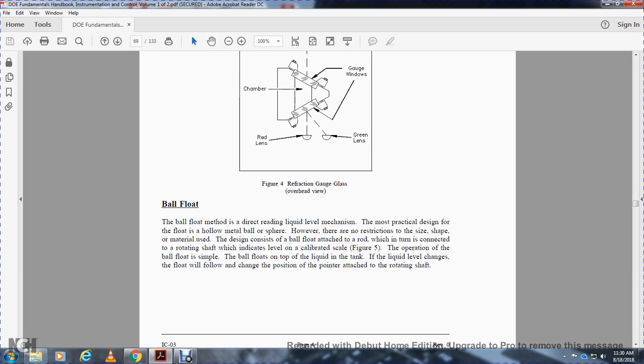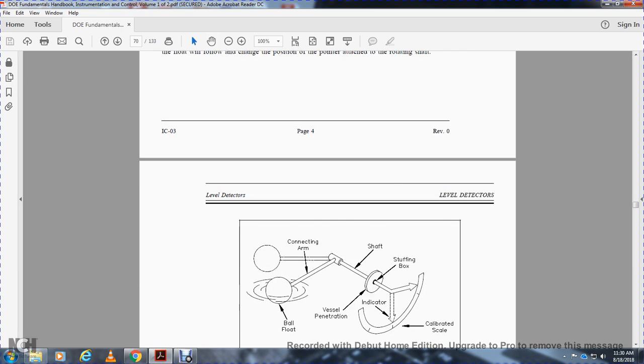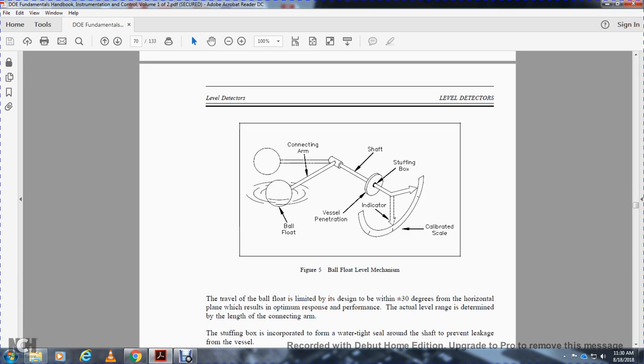The operation of the ball float is simple. The ball floats on top of the liquid in the tank. If the liquid level changes, the float will follow the level, and the position of the pointer attached to the rotating shaft changes. This shows the ball float with the connecting arm, the shaft, the stuffing box, and the vessel penetration and calibrated scale.